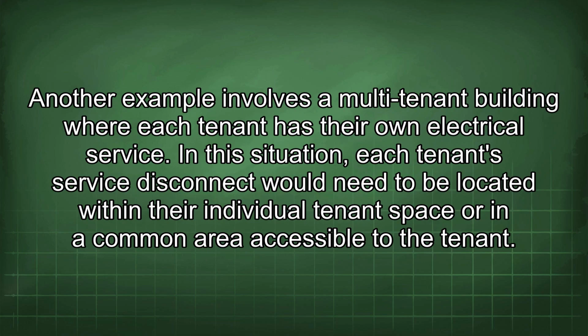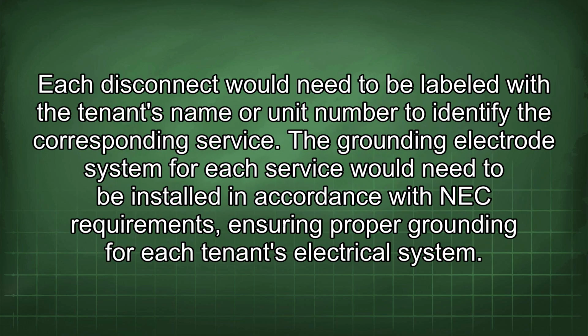Another example involves a multi-tenant building where each tenant has their own electrical service. In this situation, each tenant's service disconnect would need to be located within their individual tenant space or in a common area accessible to the tenant. Each disconnect would need to be labeled with the tenant's name or unit number to identify the corresponding service. The grounding electrode system for each service would need to be installed in accordance with NEC requirements, ensuring proper grounding for each tenant's electrical system.